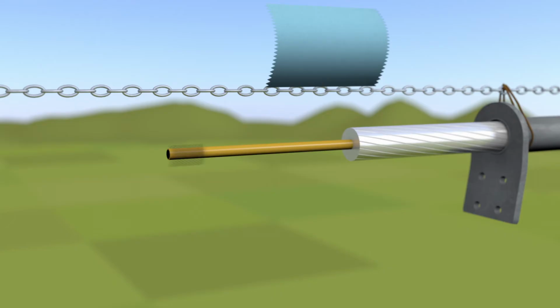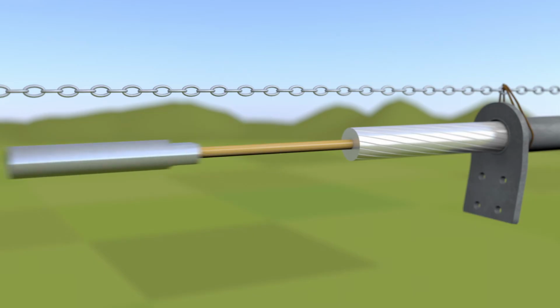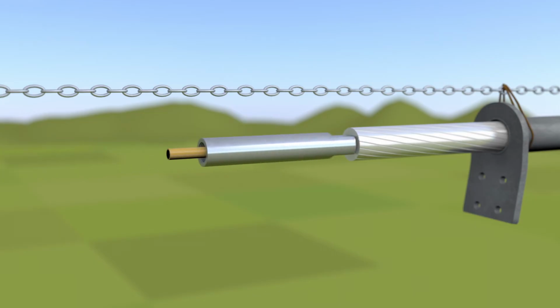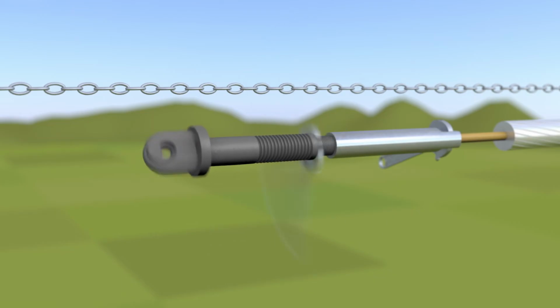The core needs to be cleaned, sanded, and then cleaned again before mounting the collet. We slide the collet housing over the core towards the aluminium strands. Then we install the collet, moving it towards the housing, leaving part of the core exposed. A clevis can now be screwed onto the collet housing and tightened using suitable wrenches.